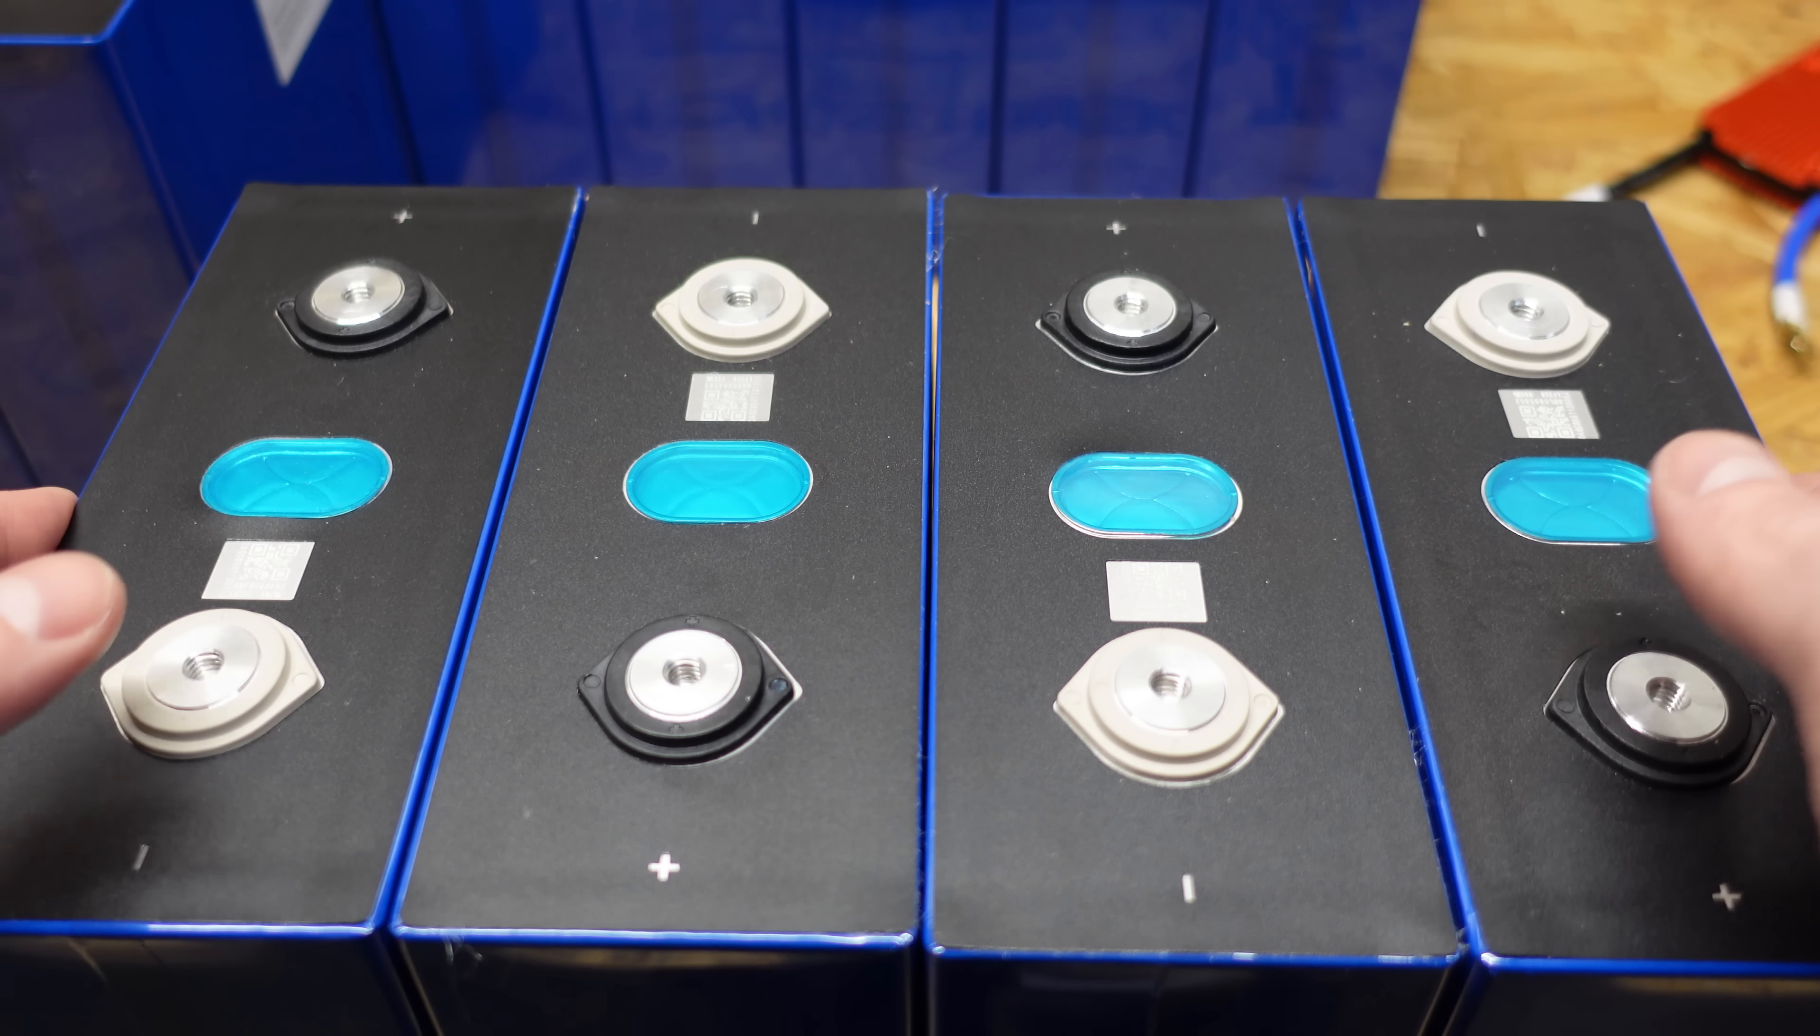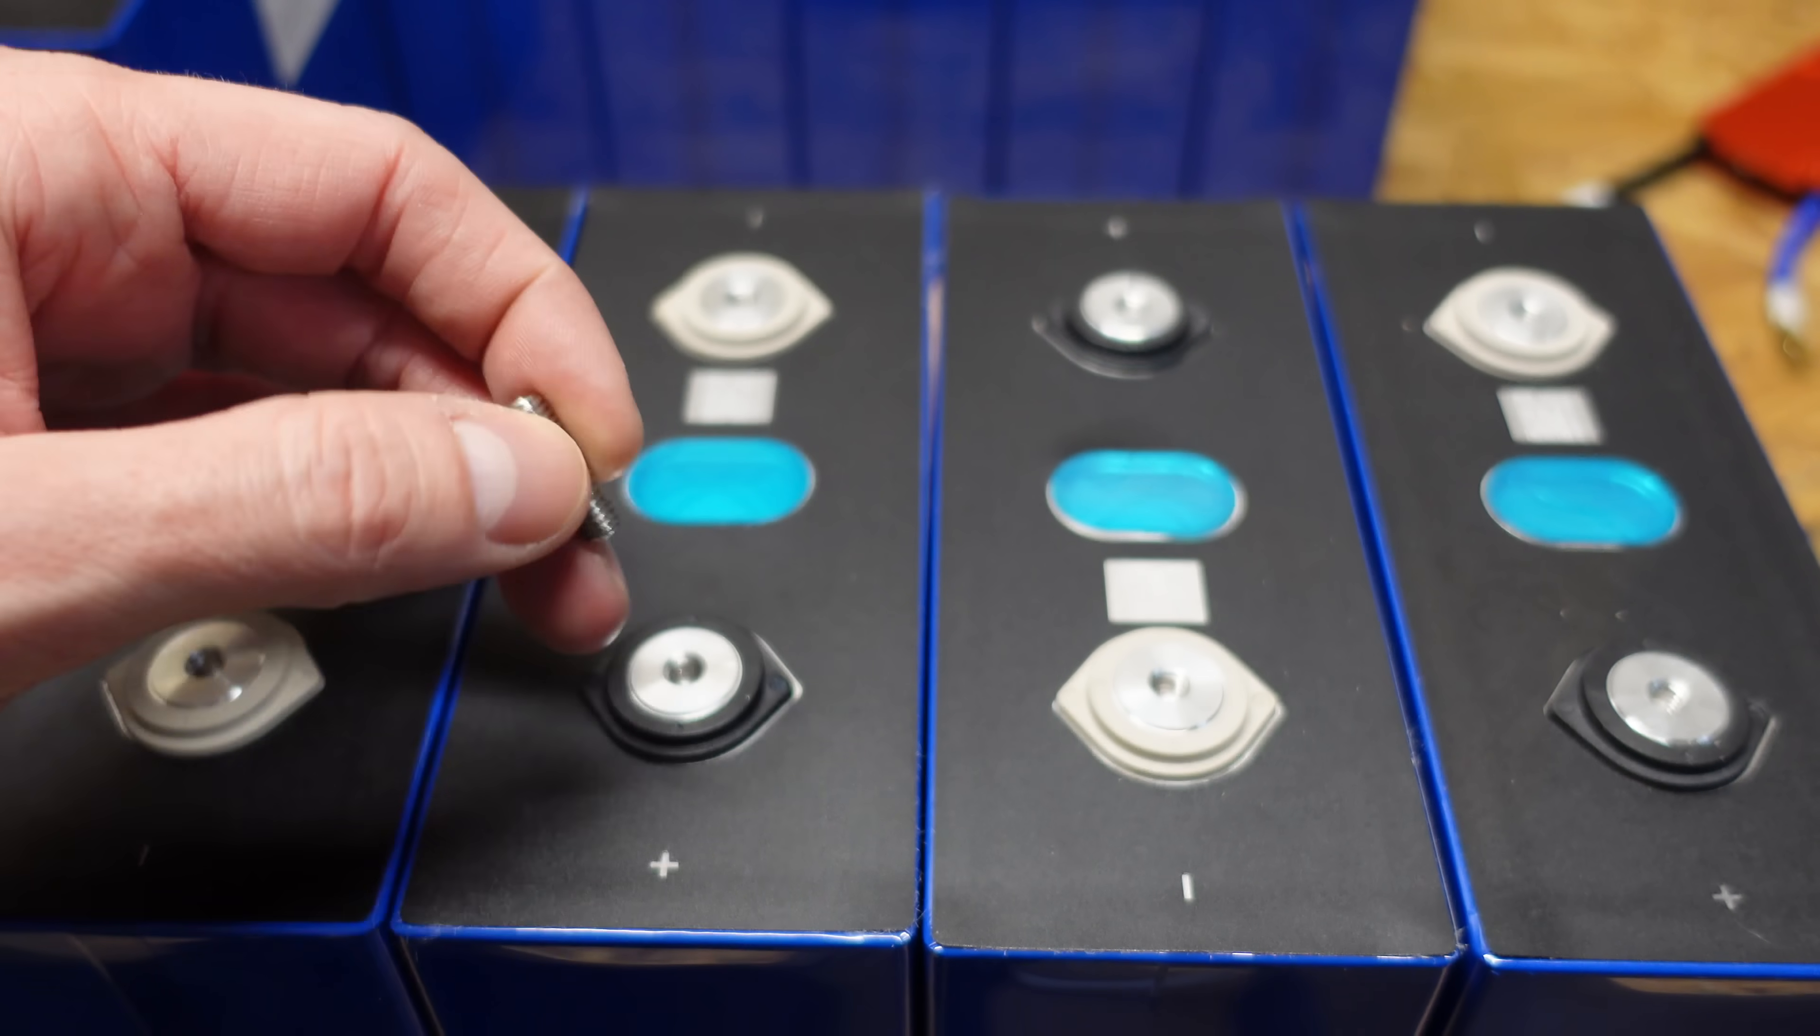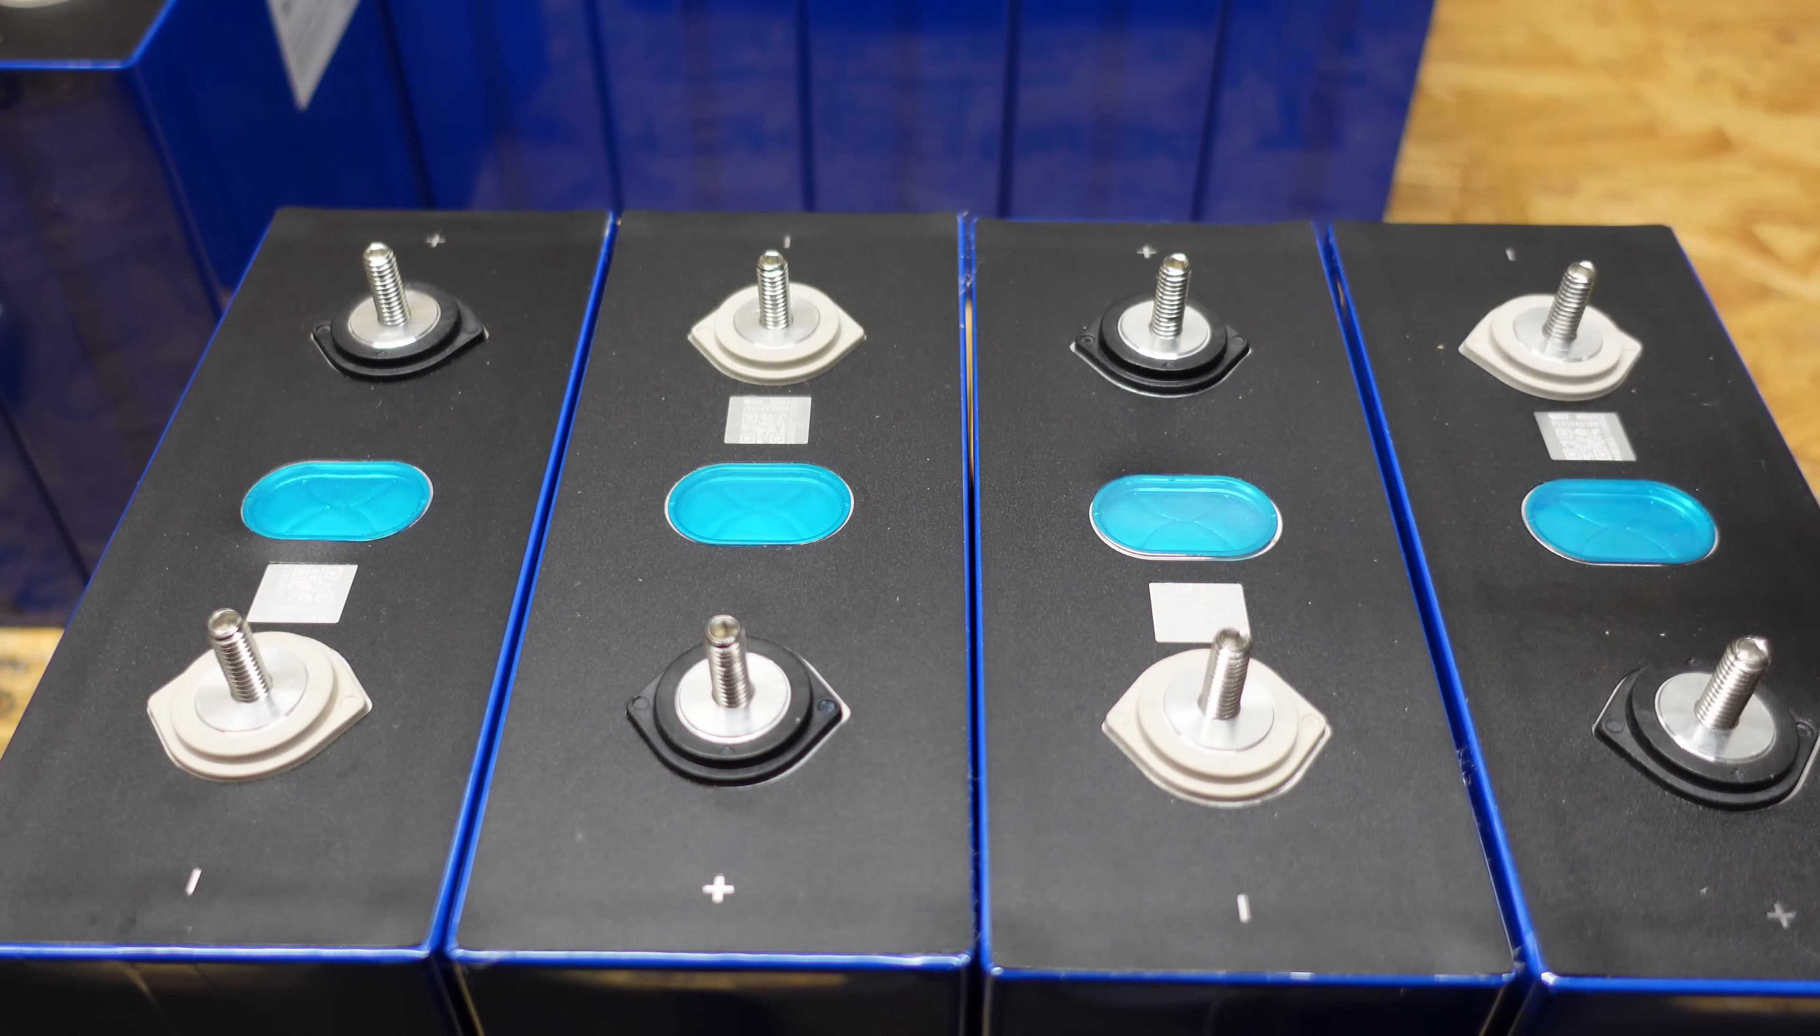All right. So now we're going to wire four of these in a 12-volt block, and we're going to show you how to do that. And then we're going to begin the capacity test, which is usually the part people are most interested in seeing. So I'm going to thread one of the stainless steel studs into each cell just by hand. And I'm leaving the allen head part pointed upward.